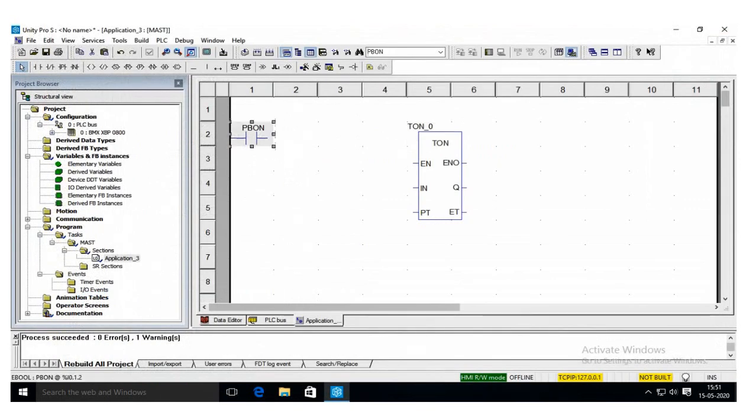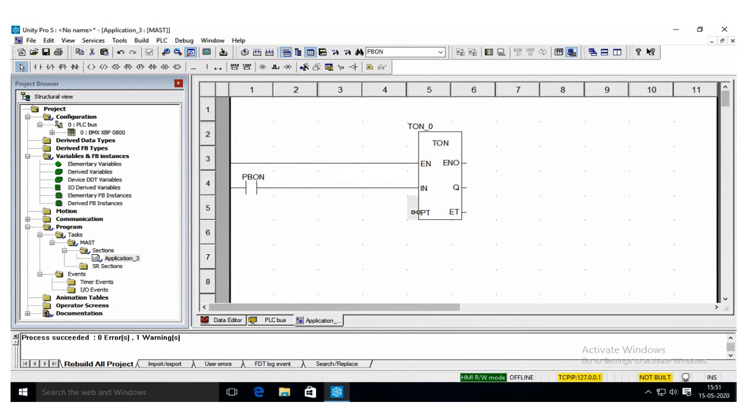So the PBON is the input for that, and here the enable is connected directly to the power rail. The delay PT—in the delay is 10 seconds, a lamp switched on after 10 seconds. Click this and here you have to give the delay, so 10 seconds. Type 10s. If you type it, it automatically takes t as 10 seconds.